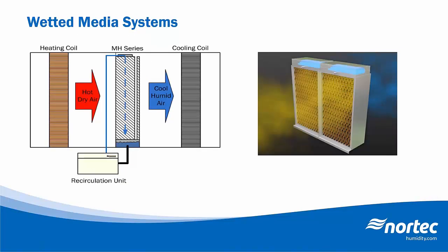So let's take a look at each of these technologies in a little bit more detail, starting with a wetted media system. So this type of system uses a wetted media pad placed directly near the airstream. And typically this media is going to be a glass fiber media or polyester media, sometimes even a cellulose or paper-based media. But the media is effectively saturated with water. As warm, dry air passes through the media, water is evaporated, and we get cool, humidified air on the discharge side. Now, all the evaporation in this type of system occurs within the depth of the media pad itself.